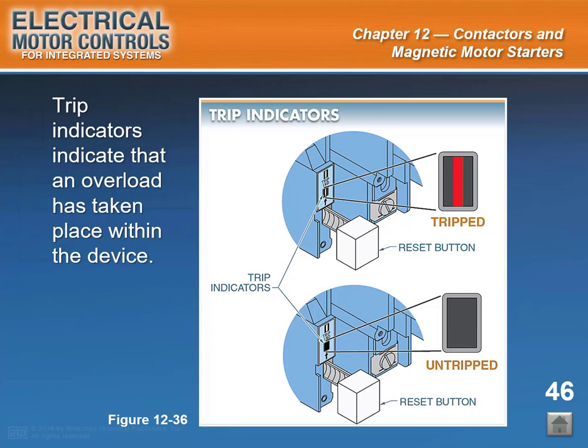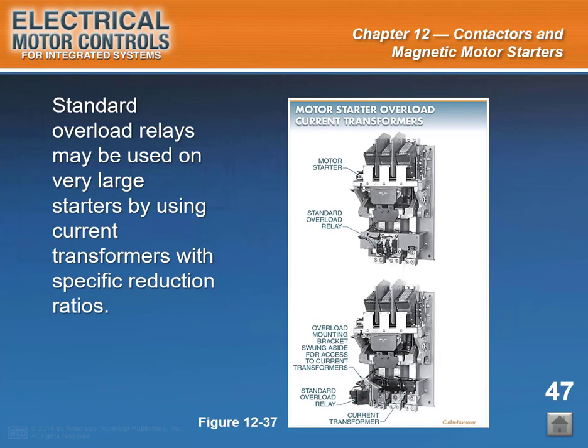End of slide 46. Start of slide 47. Slide caption: standard overload relays may be used on very large starters by using current transformers with specific reduction ratios. See figure 12-37. Large horsepower motors have currents that exceed the values of standard overload relays. To make the overload relays larger would greatly increase their physical size, which would create a space problem in relation to the magnetic motor starter. To prevent such a conflict, current transformers are used to reduce the current in a fixed ratio.